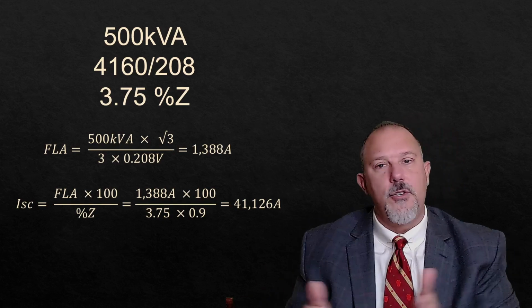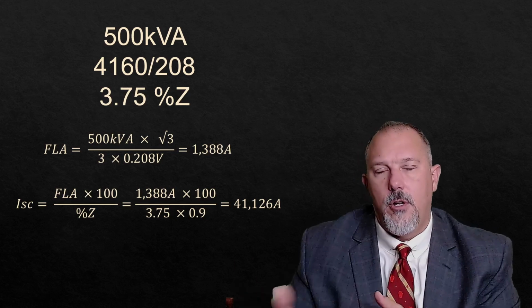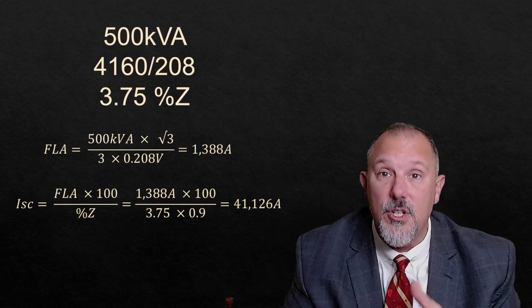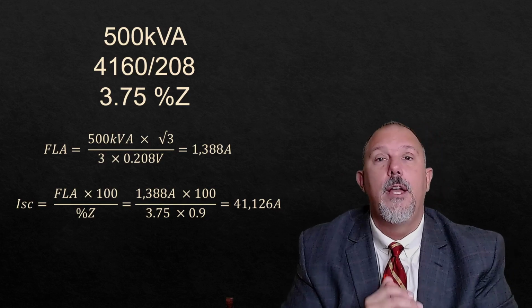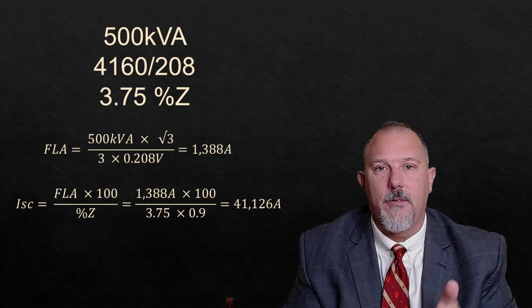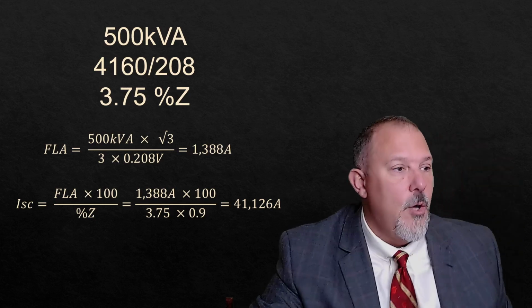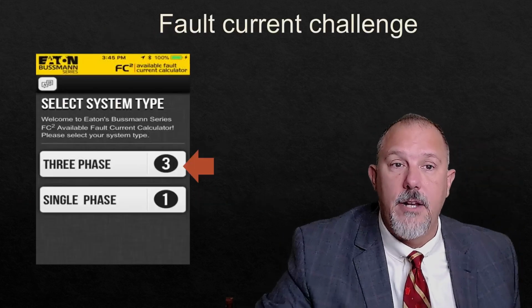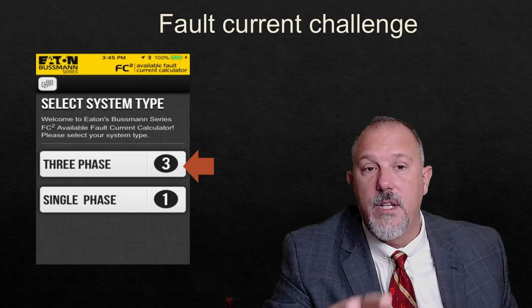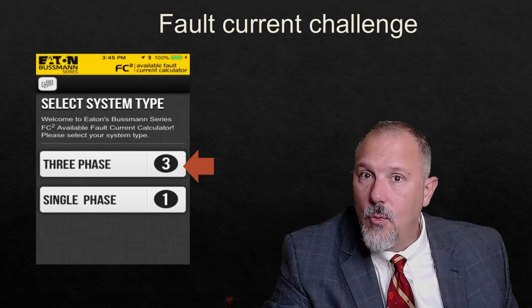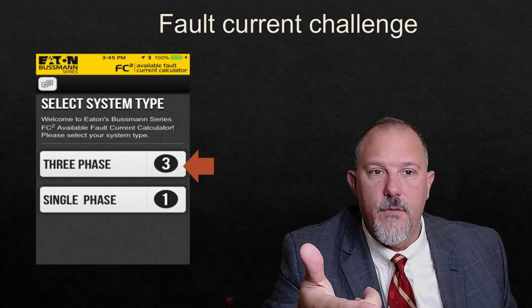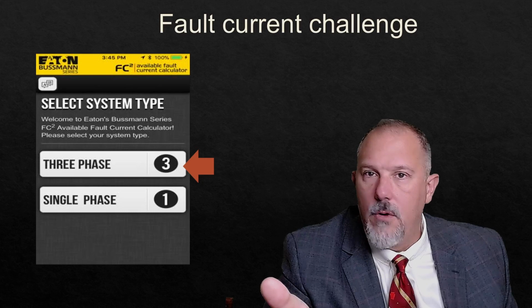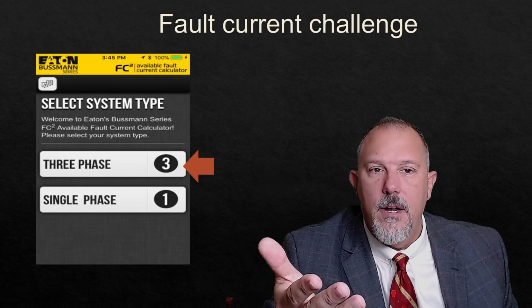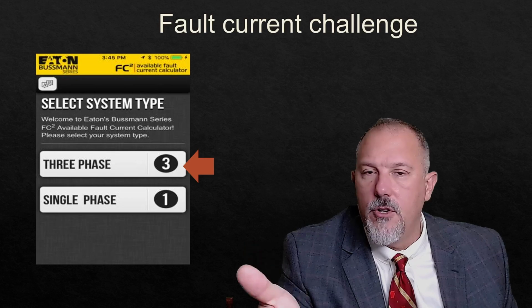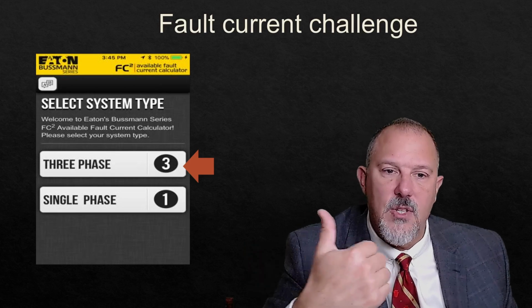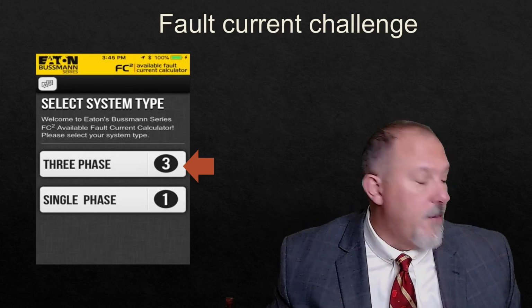And then you add conductors and it's more of a long and drawn out calculation, but there are free tools that you can download and use to calculate fault current throughout a power distribution system, or get an estimate. One of those is the fault current calculator, which I know you've all seen. It's a Bussmann tool that is free on your iPhone, your Android, or on the web. Google it, look for FC2, or search for Bussmann FC2 available fault current calculator. You'll find it, download it. These are screenshots on your typical iPhone.